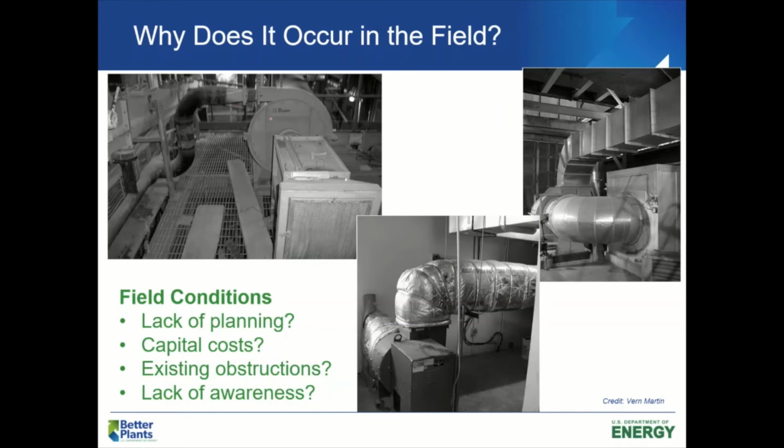So, everything from, you can see with our example in this top left-hand corner, it's shooting air out, but immediately we're turning direction, and we're then pumping into this teed header, right? So there's a big pressure drop right here. We're just slamming that air right into the pipe all the time. But up here, the fact that we're turning and twisting nonstop, that's not good.